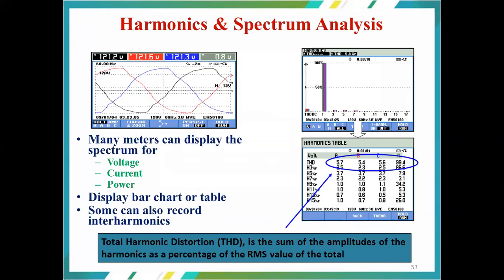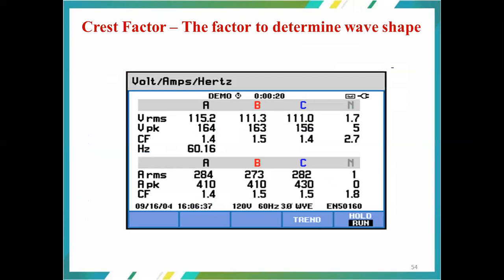So, the harmonic spectrum and the analysis. Many meters can display the spectrum for voltage, current, and power, in a bar chart or in numerical values depending on the particular equipment. As far as India is concerned, we rely on harmonic analyzers of CAT II or CAT IV categories. And this is the crest factor to determine the wave shape. Once the wave shape is better, we can assume that the input supply quality is comparatively better.